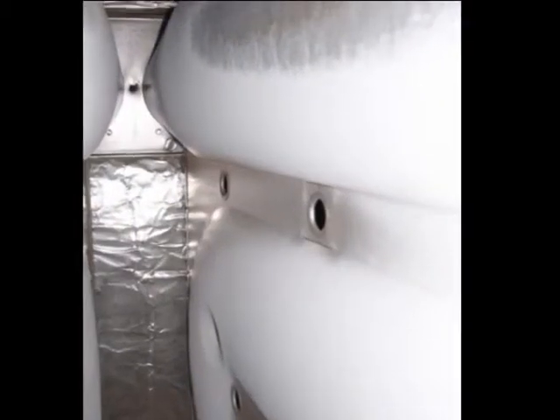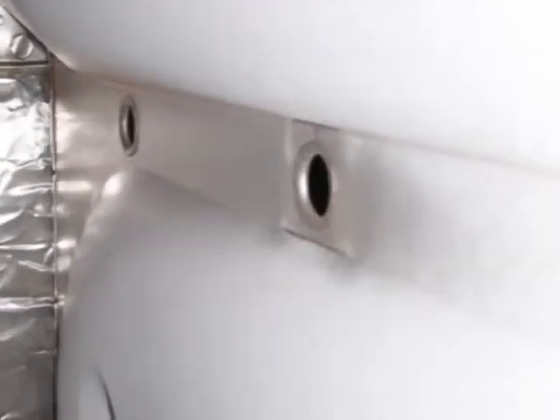With these furnaces, typically the biggest problem is these eyelets. I don't know if you can see — I'm going to try to zoom in. These eyelets right here — it's not so much a problem with mid-efficient furnaces, it's more so with high-efficient ones, but I've seen it with these mid-efficient furnaces too. What will happen is cracks will start to form around them, or more often than not the eyelet itself, that little shiny piece of circle there, will actually fall out.